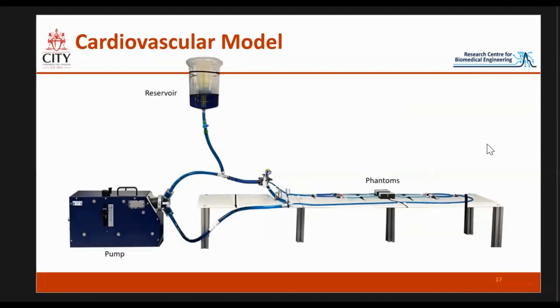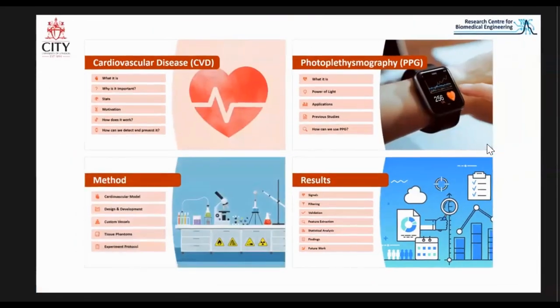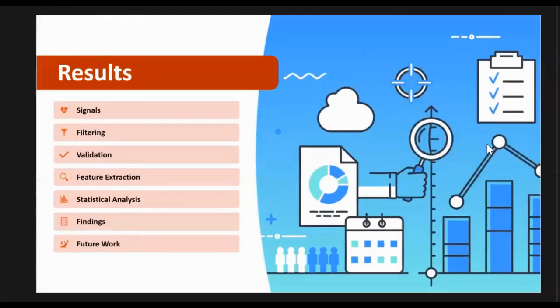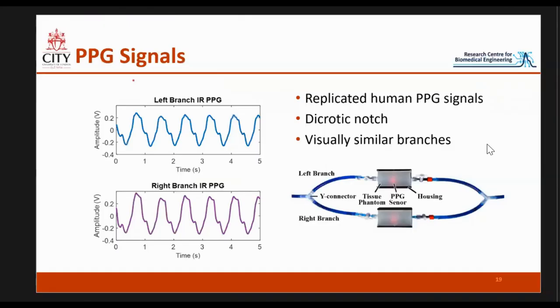This is what it looks like in practice — the final product with the pump, the reservoir, and our phantoms. The initial findings were more of a validation study, just to see if we can obtain human-like PPGs from both sides and whether they are similar. These are examples of the infrared signals. We successfully obtained human-like PPG with a dicrotic notch as well, and they look visually similar — so that was good news.